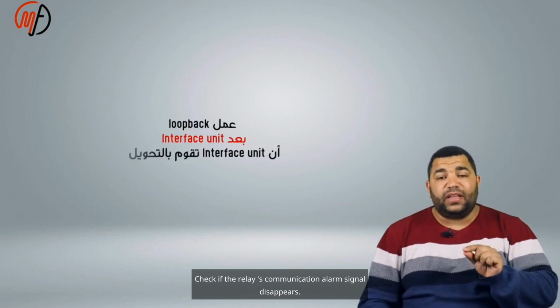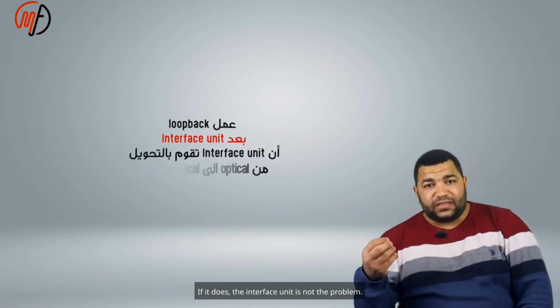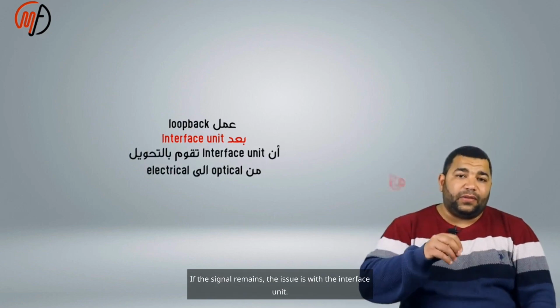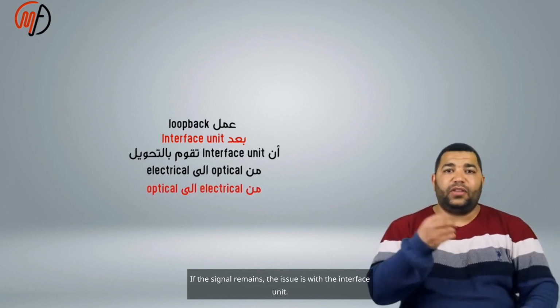Check if the relay's communication alarm signal disappears. If it does, the interface unit is not the problem. If the signal remains, the issue is with the interface unit.